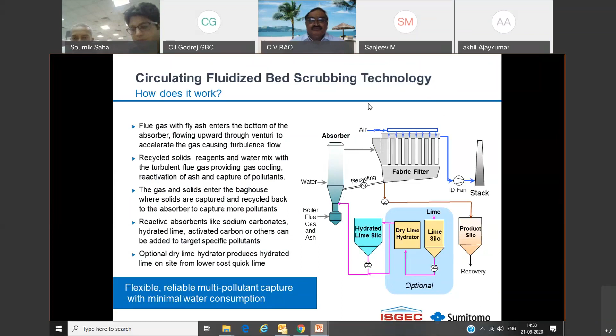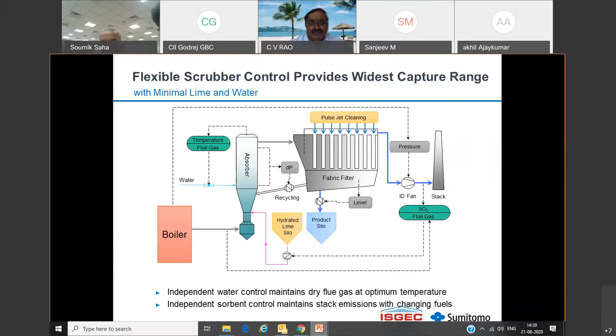Okay, so this is the schematic we are showing. Typically, the control is very simple here. There is an independent water control which maintains the flue gas temperature, which is optimum for the reaction. The main control circuit is solid recirculation, which is maintained for proper reagent utilization. And then we have limestone injection control through SO2 feedback. We take feedback from SO2 and feed the required amount of hydrated lime to control the same.